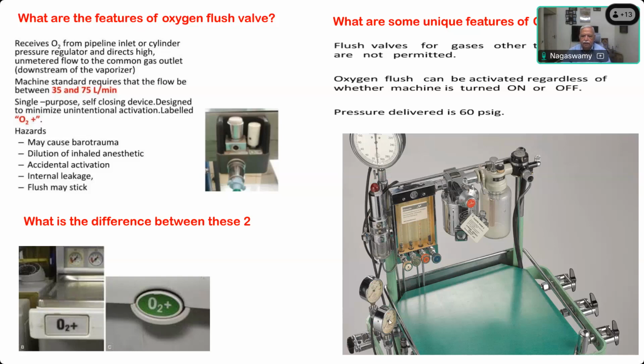So I am tracing it. These are pressure gauges. This is the flow meter. This is the vaporizer. This is the common gas outlet. Where is the oxygen flush activator? So this is the on-off knob, sir. We have to rotate it down or up. In the up position it is off. In the down position it will be on.